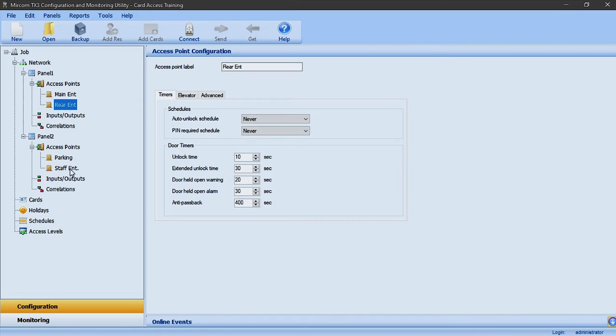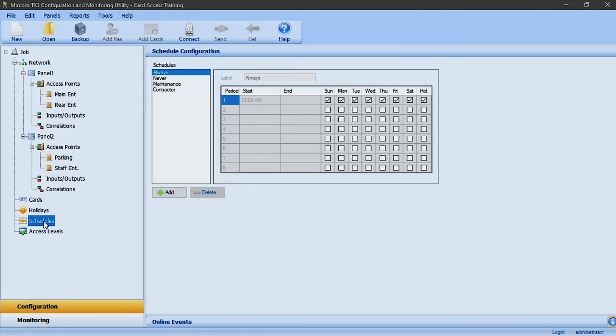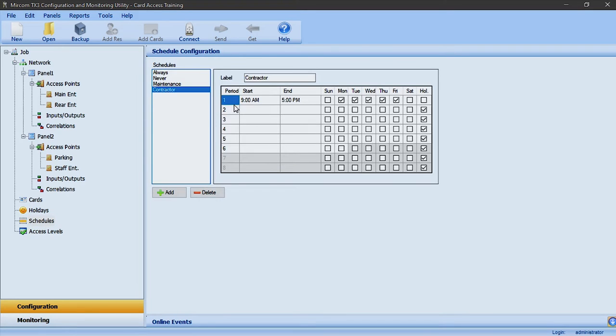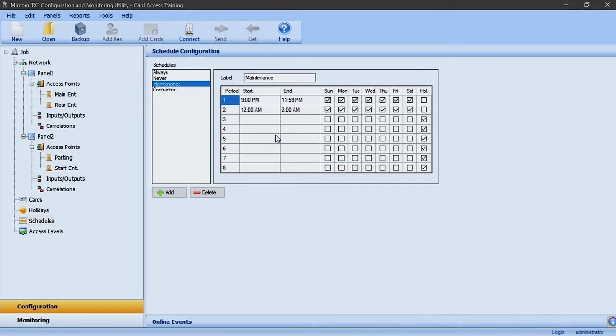Before entering the access credential data I like to create schedules and access levels. In the schedules section of the job tree I have created a maintenance staff and contractor example schedule. Contractors are scheduled to work in the building from 9 a.m. to 5 p.m. Monday to Friday, and the maintenance staff are scheduled to enter the building overnight from 9 p.m. to 2 a.m. Sunday to Saturday. Please note that when creating overnight schedules, two periods must be used as per the maintenance schedule I have created.